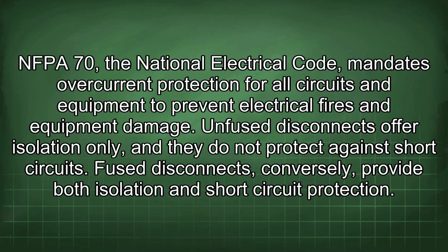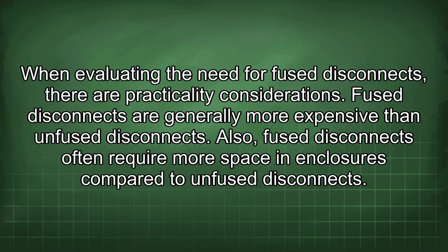NFPA 70, the National Electrical Code, mandates overcurrent protection for all circuits and equipment to prevent electrical fires and equipment damage. Unfused disconnects offer isolation only, and they do not protect against short circuits. Fused disconnects, conversely, provide both isolation and short circuit protection. When evaluating the need for fused disconnects, there are practicality considerations.